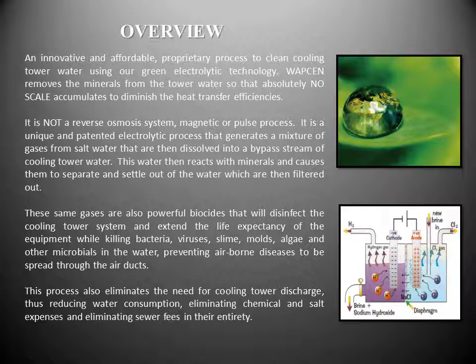It is not a reverse osmosis system, magnetic or pulse process. It is a unique and proprietary electrolytic process that generates a mixture of gases from salt water that are then dissolved into a bypass stream of cooling tower water. This water then reacts with minerals and causes them to separate and settle out of the water, which are then filtered out.